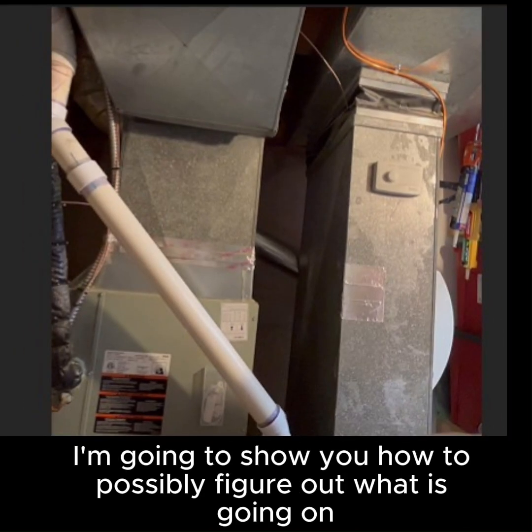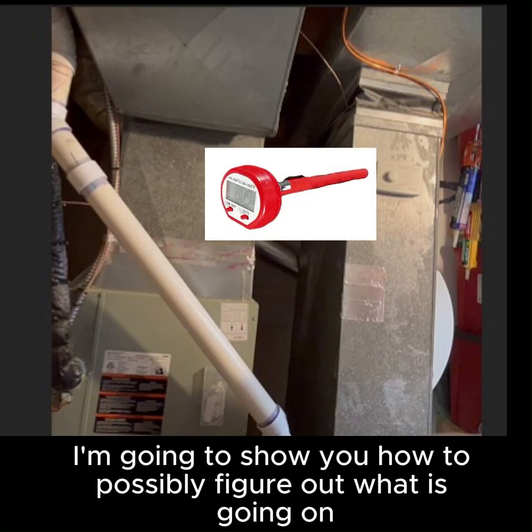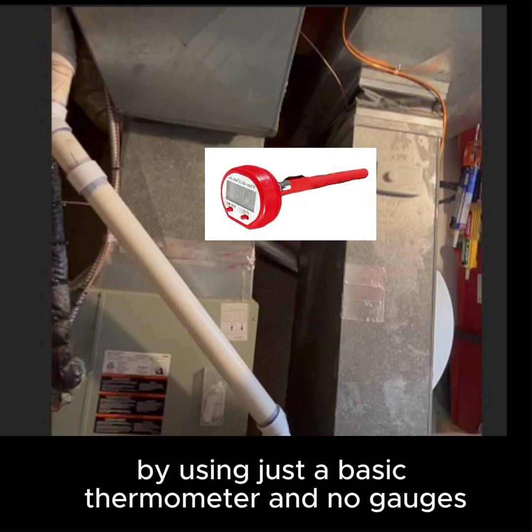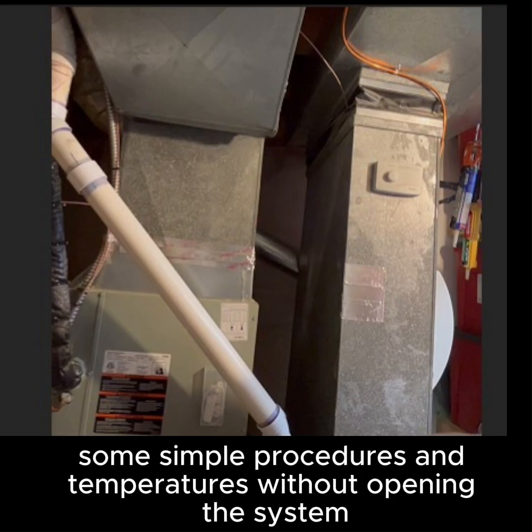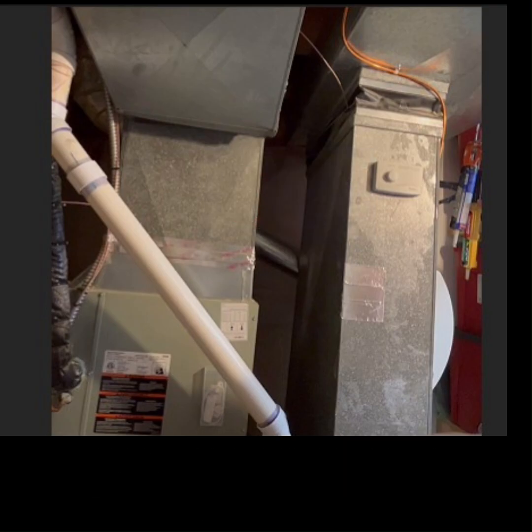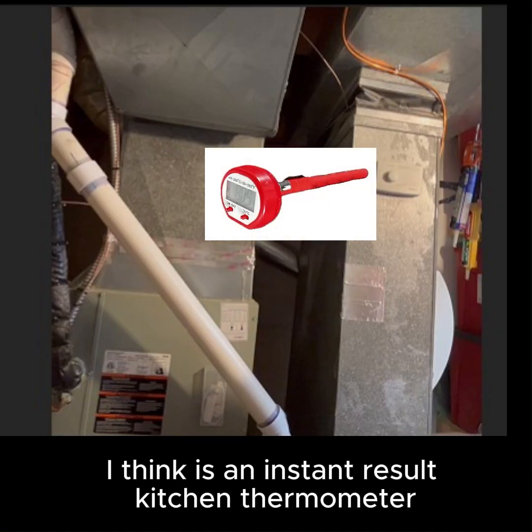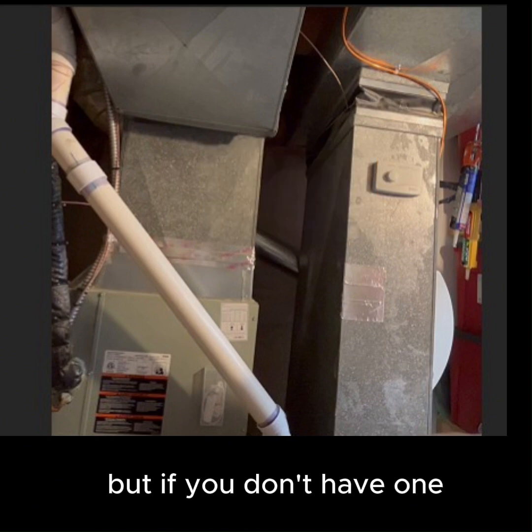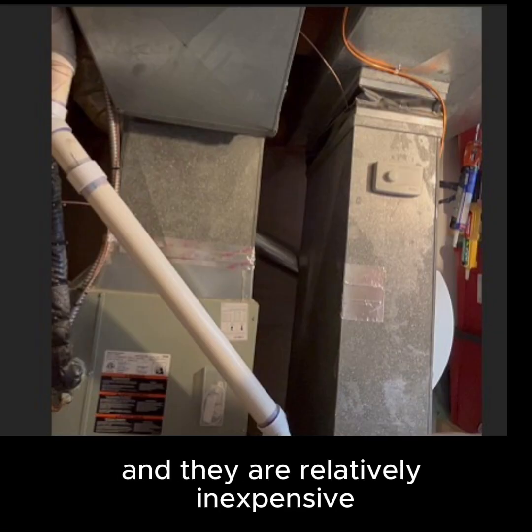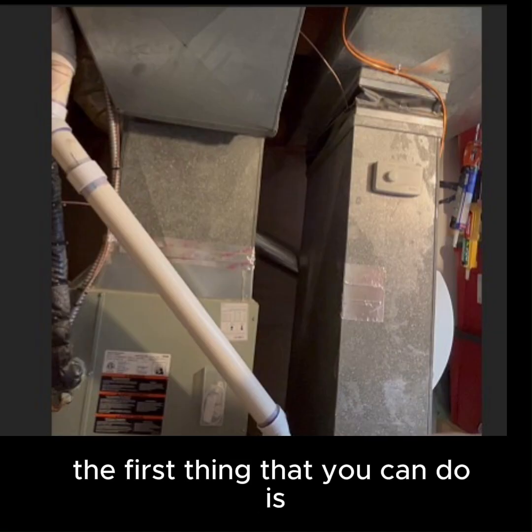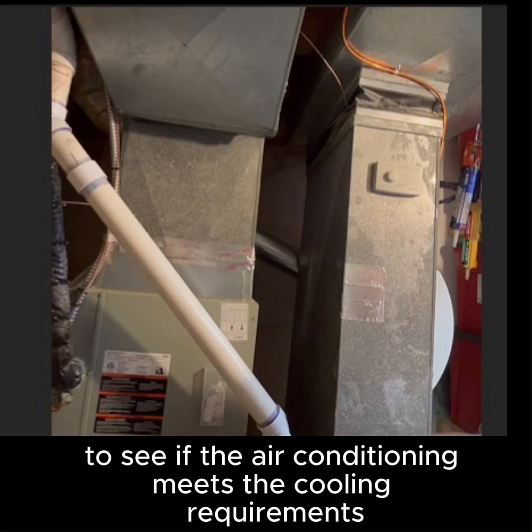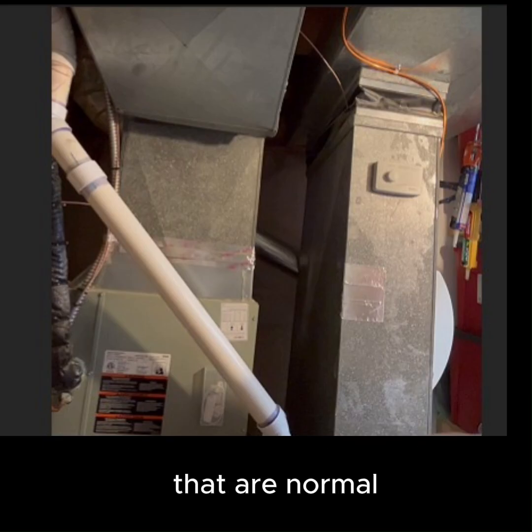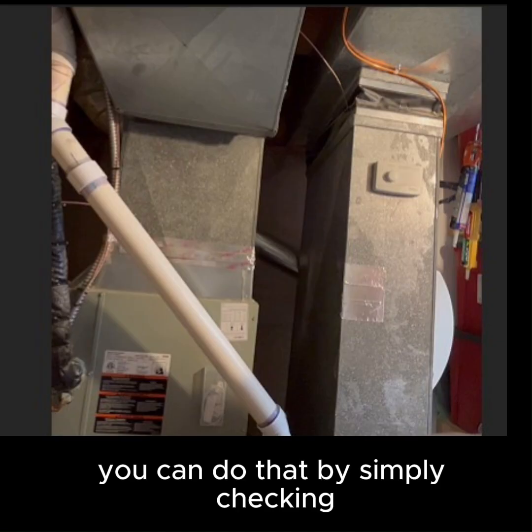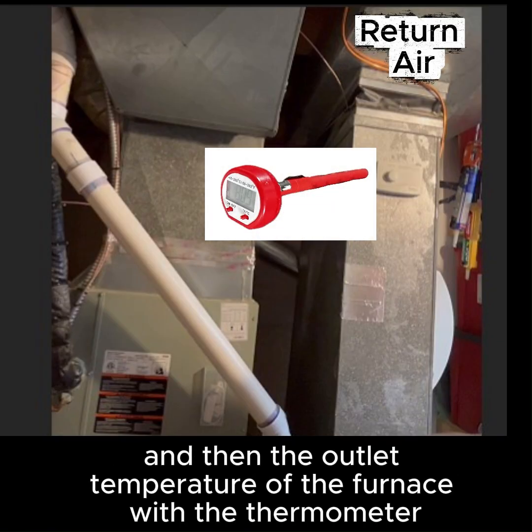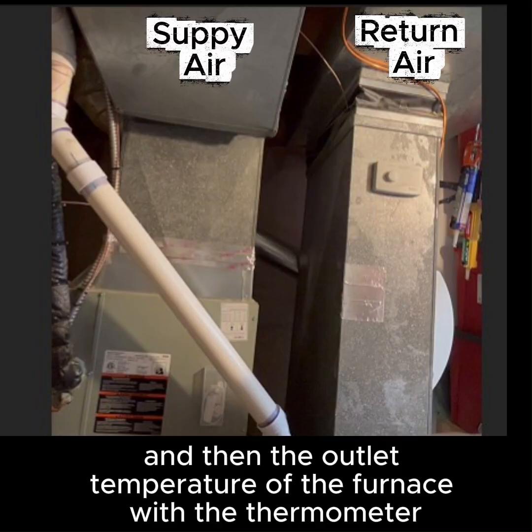Today, I'm going to show you how to possibly figure out what is going on by using just a basic thermometer and no gauges. Some simple procedures and temperatures without opening the system. The best tool you can use, I think, is an instant result kitchen thermometer. Many people have one in their kitchen, but if you don't, you can pick one up on Amazon, and they are relatively inexpensive. The first thing you can do is check to see if the air conditioning meets the normal cooling requirements. You can do that by simply checking the inlet temperature of the furnace and then the outlet temperature of the furnace with the thermometer.